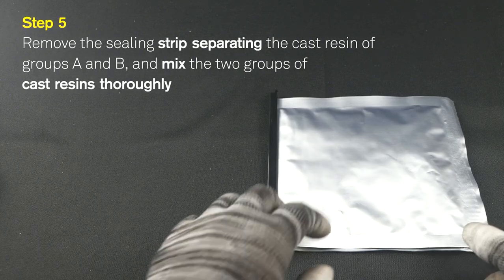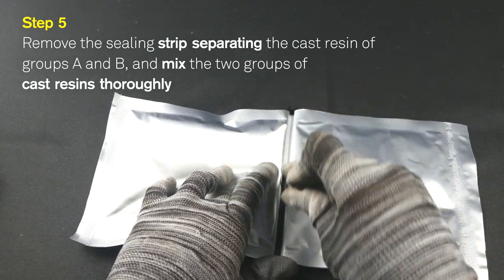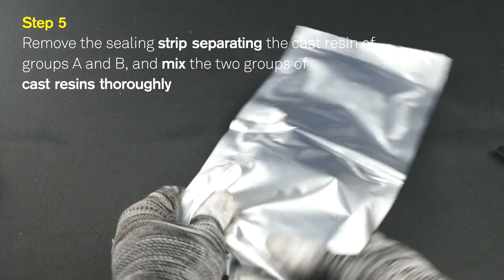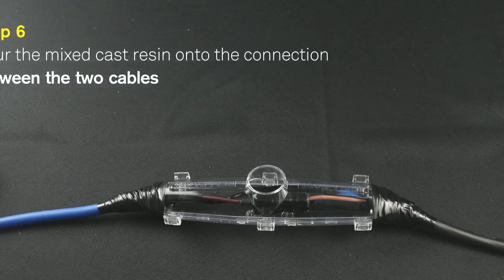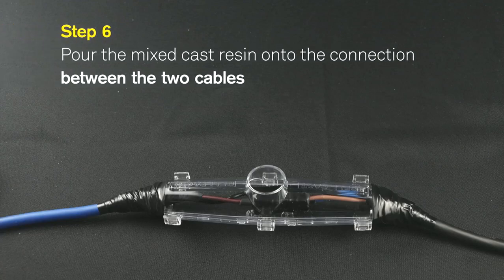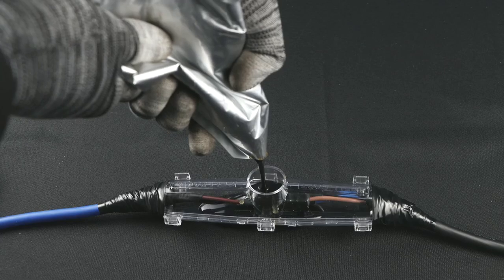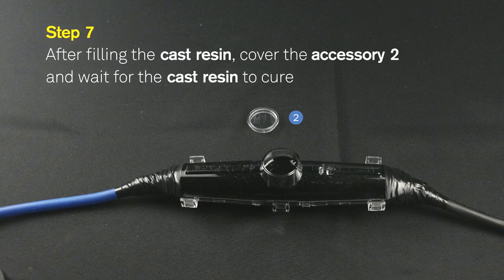Step 5: Remove the sealing strip separating the Cast Resin of Groups A and B, and mix the two groups of cast resins thoroughly. Step 6: Pour the mixed cast resin onto the connection between the two cables. Step 7: After filling the cast resin, cover the accessory 2 and wait for the cast resin to cure.